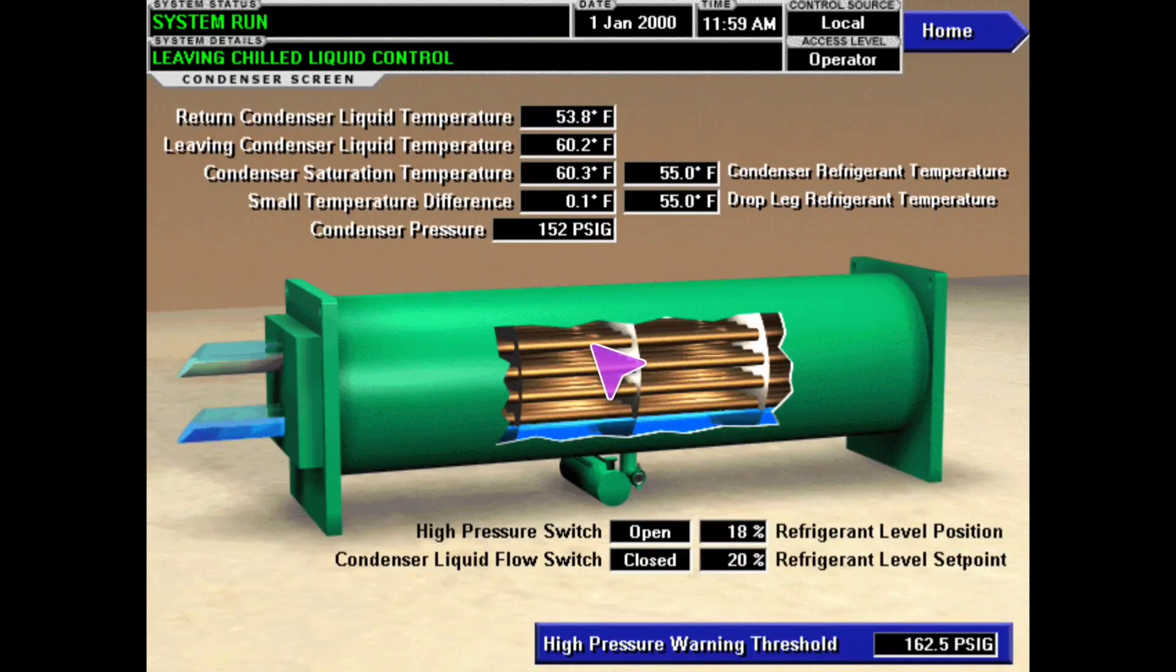This would be considered more of a flooded type design, but this is a condenser. This specifically came from a York OptiView control panel, but it made a really good example for what we're discussing here because of the small temperature difference right there. That is actually the calculated approach value.